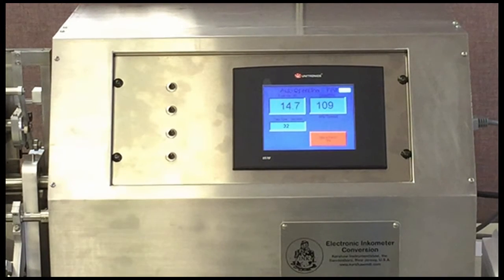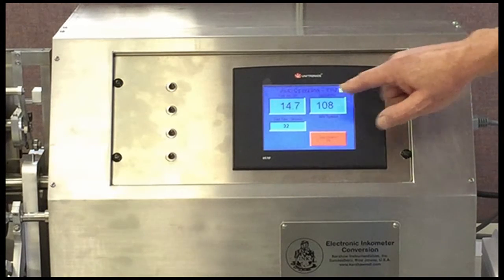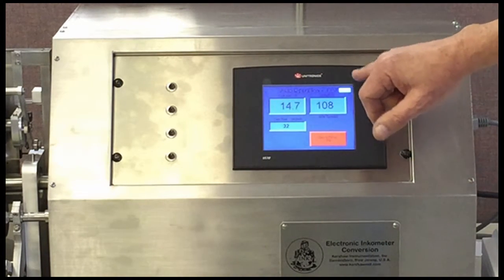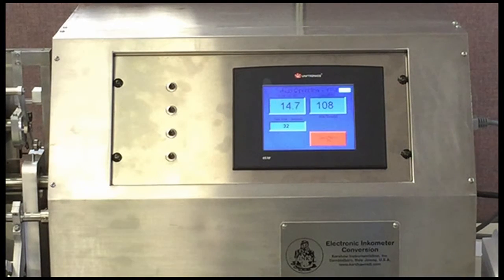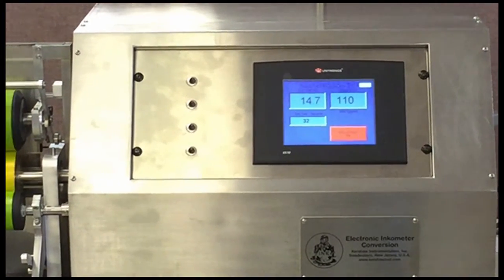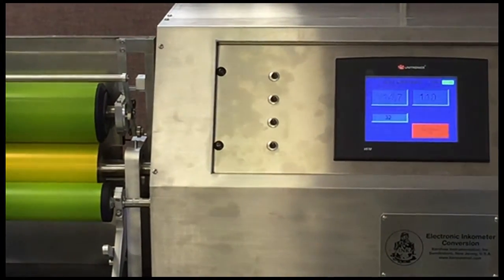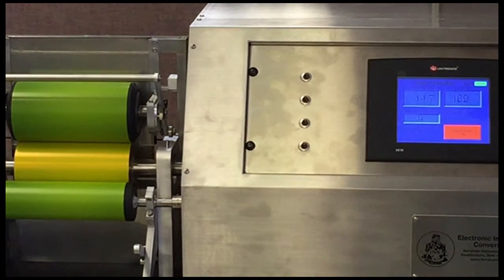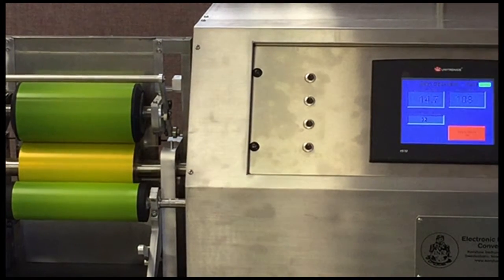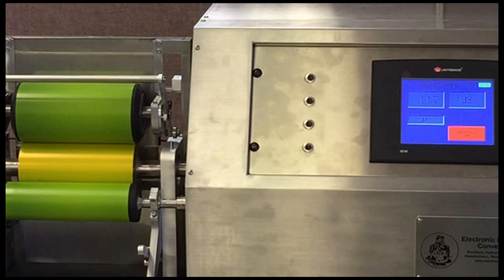In addition to that, we also have what's called a dry cal, which is a box in the same place but a different color. The dry calibration uses the calibration weights you may be familiar with. One of the niceties of this machine is the ability to calibrate using the weights and store that information, or calibrate using a tack standard ink of your choice and store that calibration data. You can select whether to run your test based on the weight calibration or the wet sample calibration.